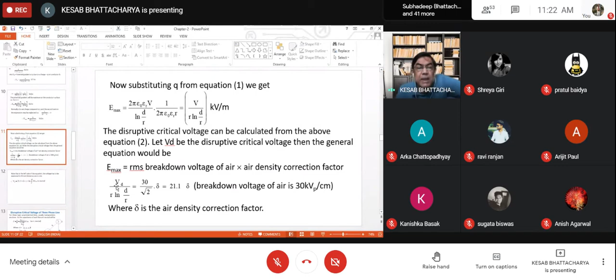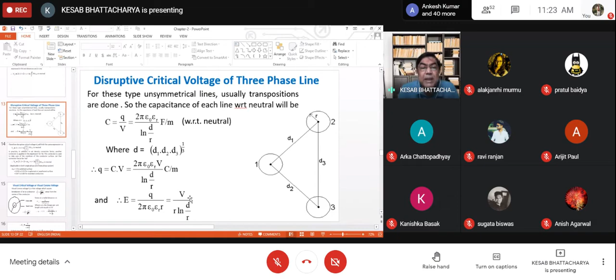Now, this is the expression for disruptive critical voltage, and for three-phase lines the expression will remain the same. The only difference is this: if the conductors of the three phases are arranged in a triangle like this, and the distances between them are d1, d2, and d3 respectively, then C is equal to Q by V, or Q is equal to CV, the same expression holds. The only thing is that here D is to be replaced by the cube root of d1 into d2 into d3. The remaining part of the expression, E equal to V by R ln d by R, all remains unchanged. The final expression also remains unchanged, 21.1 into delta into R ln d by R kV RMS to neutral, only here D is equal to the cube root of d1 into d2 into d3. Is that okay?